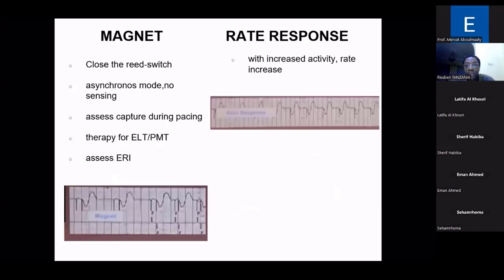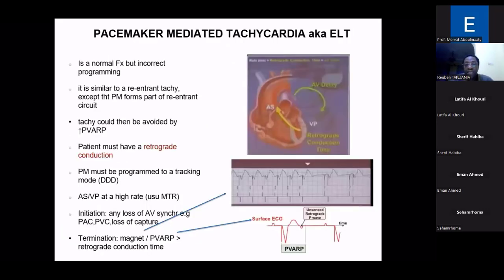There are some complications which are magnet related, like magnet rate response, and this can be due to closing of the reed switch, asynchronous mode or no sensing, and therapy for PMT and the end of ERI. Pacemaker mediated tachycardia is another common complication. It's a normal function but with incorrect programming. It is similar to reentrant tachycardia, except that the pacemaker forms part of the circuit. Tachycardia could then be avoided by increasing the PVARP. The patient must have retrograde ventriculoatrial conduction to have this pacemaker mediated tachycardia, and the pacemaker must be programmed to a tracking mode. And these are some management options. I think we can discuss this. Management of pacemaker mediated tachycardia includes a magnet. We can terminate it by magnet, or by increasing the PVARP to more than the retrograde conduction time.